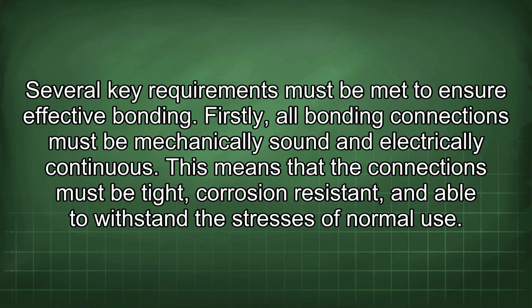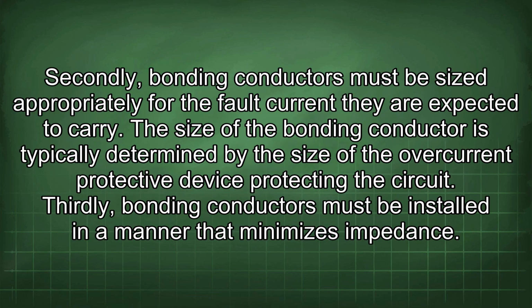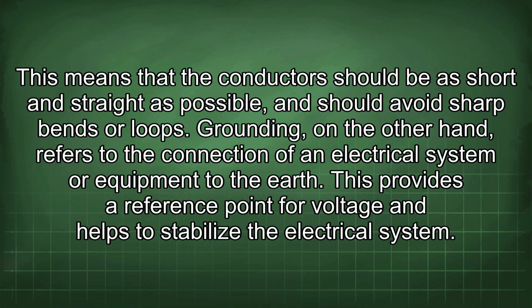Firstly, all bonding connections must be mechanically sound and electrically continuous. This means that the connections must be tight, corrosion-resistant, and able to withstand the stresses of normal use. Secondly, bonding conductors must be sized appropriately for the fault current they are expected to carry. The size of the bonding conductor is typically determined by the size of the overcurrent protective device protecting the circuit. Thirdly, bonding conductors must be installed in a manner that minimizes impedance. This means that the conductors should be as short and straight as possible and should avoid sharp bends or loops.